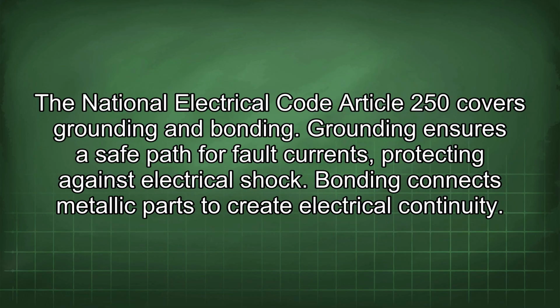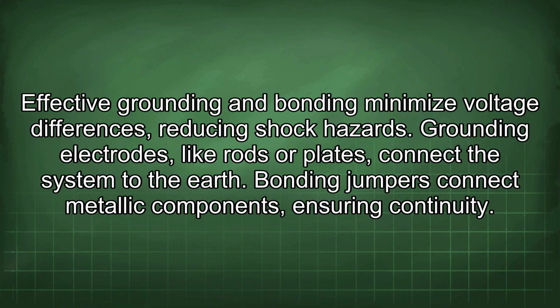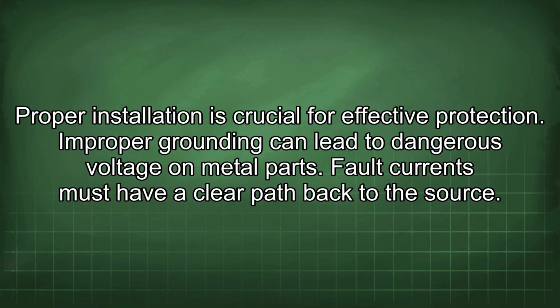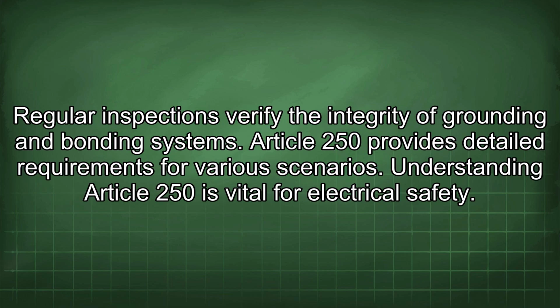The National Electrical Code Article 250 covers grounding and bonding. Grounding ensures a safe path for fault currents, protecting against electrical shock. Bonding connects metallic parts to create electrical continuity. Effective grounding and bonding minimize voltage differences, reducing shock hazards. Grounding electrodes, like rods or plates, connect the system to the earth. Bonding jumpers connect metallic components, ensuring continuity. Proper installation is crucial for effective protection. Improper grounding can lead to dangerous voltage on metal parts. Fault currents must have a clear path back to the source. Regular inspections verify the integrity of grounding and bonding systems. Article 250 provides detailed requirements for various scenarios. Understanding Article 250 is vital for electrical safety.